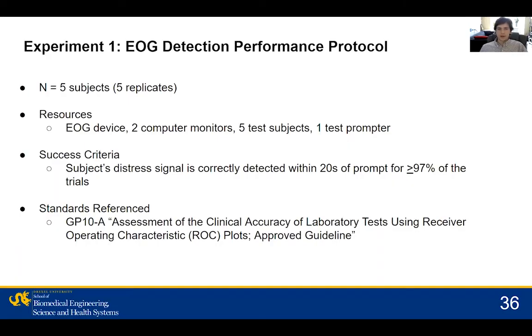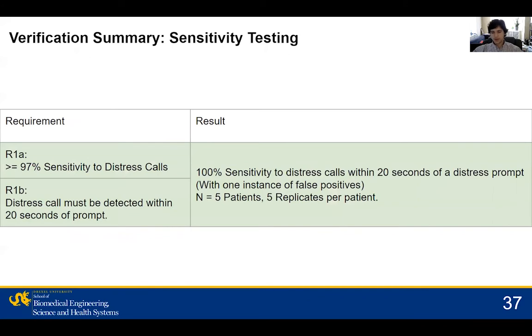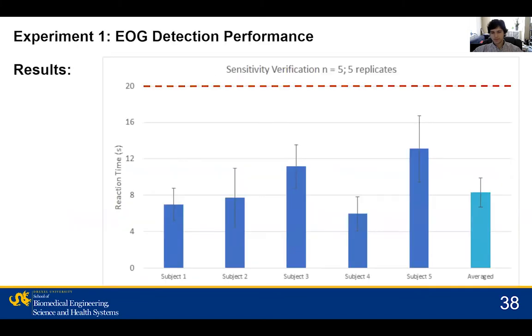Now we will cover our verification and validation process. Our first experiment was designed to test our device's sensitivity and performance. We did this through a series of monitored trials in which 5 different subjects were prompted to produce a distress signal at random intervals, repeating the process 5 times for each subject. The results of this test were to be deemed a success if users were able to generate a distress signal within 20 seconds of an alert prompt for greater than or equal to 97% of their trials. For the construction of this protocol, CLSI standard GP10A was referenced. The results of this test showed 100% sensitivity to distress calls, with each alert attempt being recognized by our device within 20 seconds, thus meeting requirements 1A and 1B.